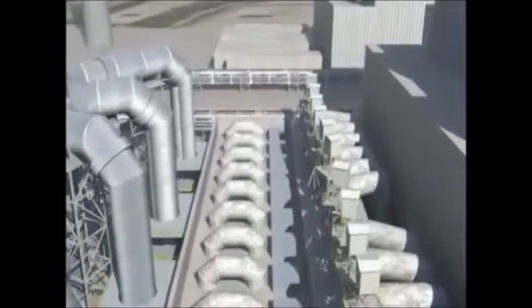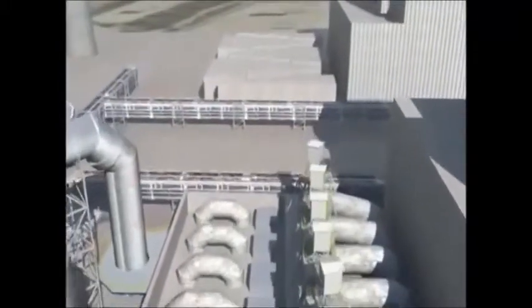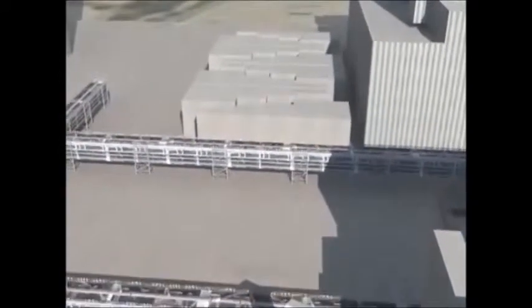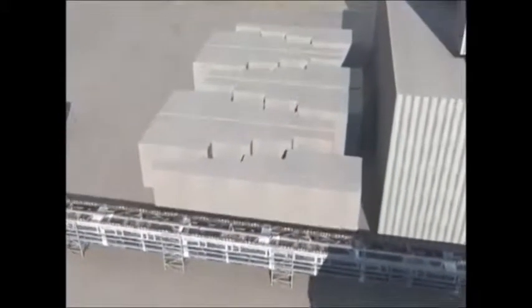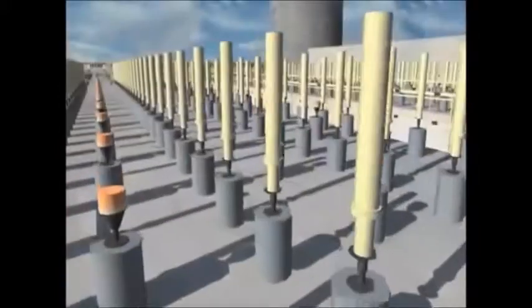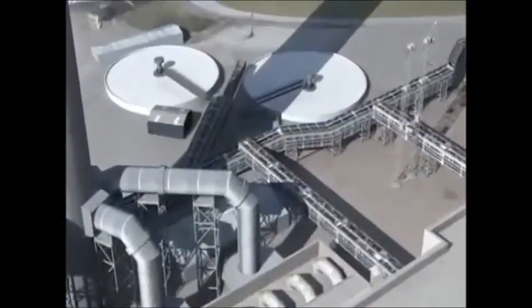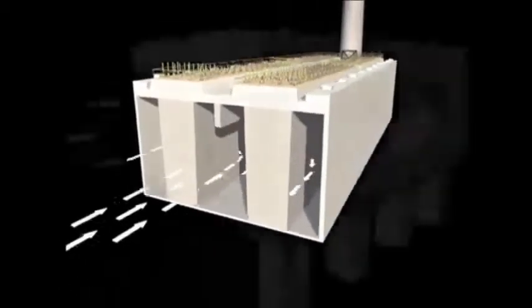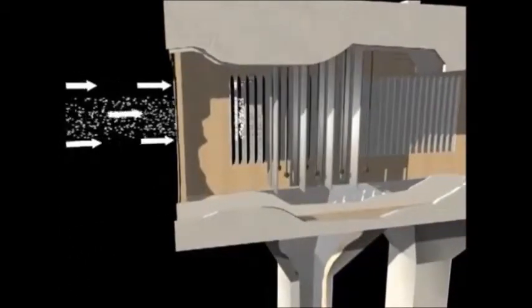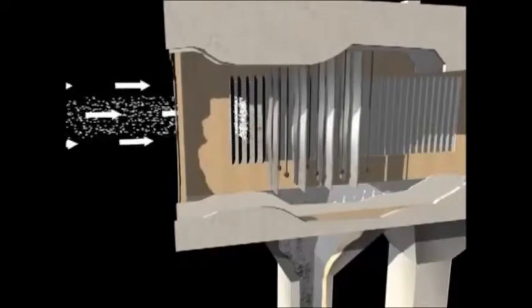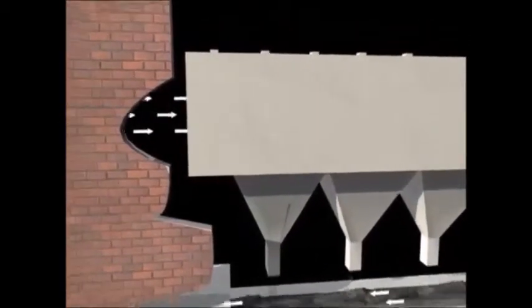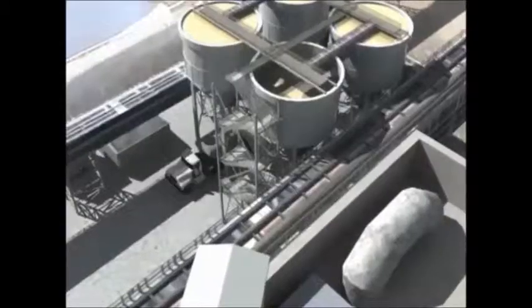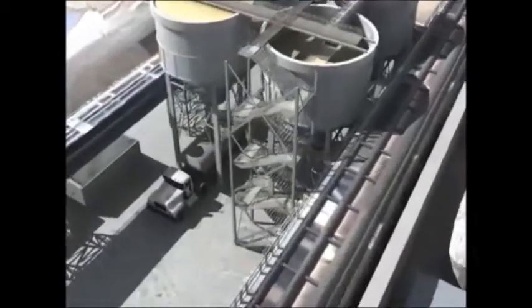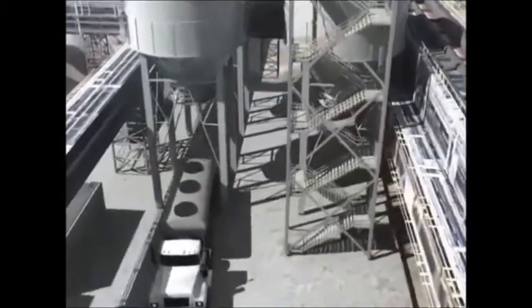Precipitators are another method of extracting coal ash, also called fly ash, which can be recycled or deposited in landfills. This mechanical process extracts fly ash left over from the combustion process. These poles, called rappers, shake fly ash from a vibrating wire. Gas from the furnace, containing fly ash, flows into the box. The fly ash drops into a storage chamber and is blown into silos to be loaded into a truck. Fly ash from FirstEnergy plants is used in manufacturing a variety of products, including concrete, grouting, roofing shingles, granules, and anti-skid road materials.